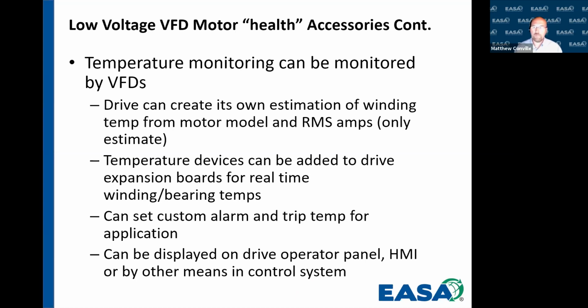Temperature can be monitored by variable frequency drives. We have several different ways that we can do that. Some drives are smart enough to create their own winding temperature from the motor model and the amount of current that's actually being given to the machine. The downfall to this method is that it assumes a temperature rise that you have to input, and it assumes that it's constantly getting the appropriate airflow or velocity, and the temperature of the cooling air is sufficient.